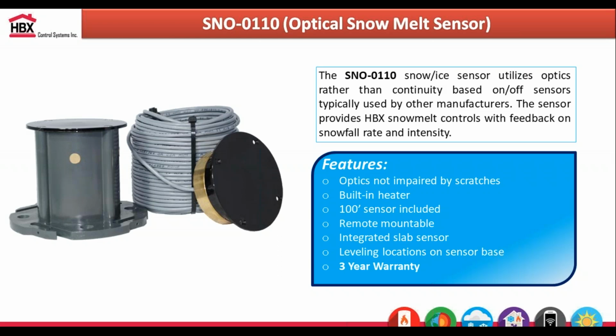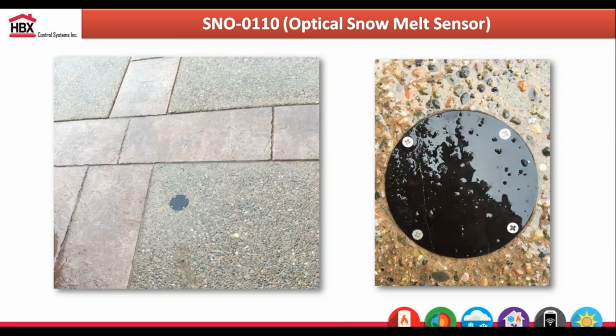So how that works functionality-wise is that the optical sensor has a built-in heater. So when it's cold outside and in the winter months, it's going to be turned on all the time. We have an outdoor sensor that works in conjunction with our snowmelt controller, telling it that we're below freezing, we're going to be turning on, and this turns on the heater in the optical sensor. This heater puts off a lot of heat. Usually when it's been running for more than 1 hour, it's putting off about 80 to 90 degrees Fahrenheit of heat. So it gets pretty warm.